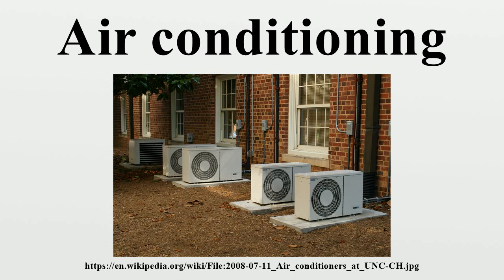The heat pump is added because the temperature of the storage gradually increases during the cooling season, thereby declining its effectiveness. Free cooling systems can have very high efficiencies, and are sometimes combined with seasonal thermal energy storage, so the cold of winter can be used for summer air conditioning. Free cooling and hybrid systems are mature technology.